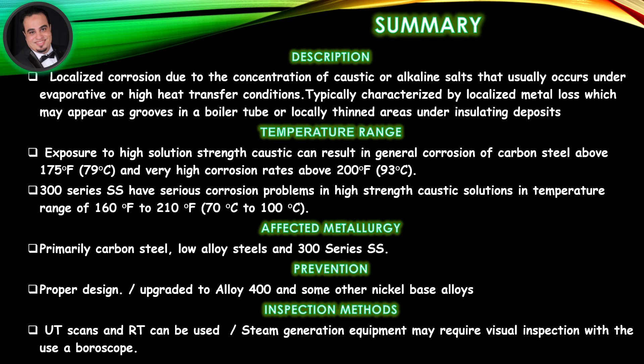Summary — Temperature range: Exposure to high solution strength caustic can result in general corrosion of carbon steel above 175°F, and very high corrosion rates above 200°F. 300 series stainless steel has serious corrosion problems in high-strength caustic solutions in the temperature range of 160°F to 210°F. Affected metallurgy: primarily carbon steel, low alloy steels, and 300 series stainless steel. Prevention: proper design, or upgrade to Alloy 400 and some other nickel-base alloys.